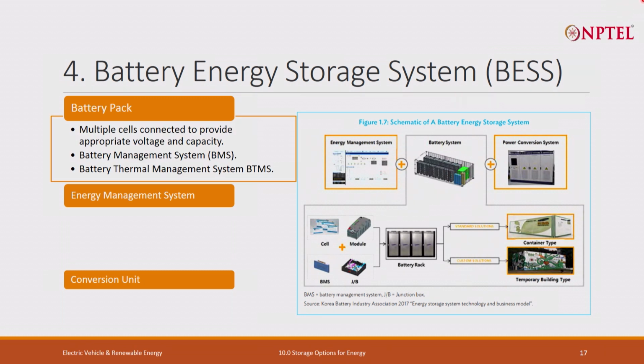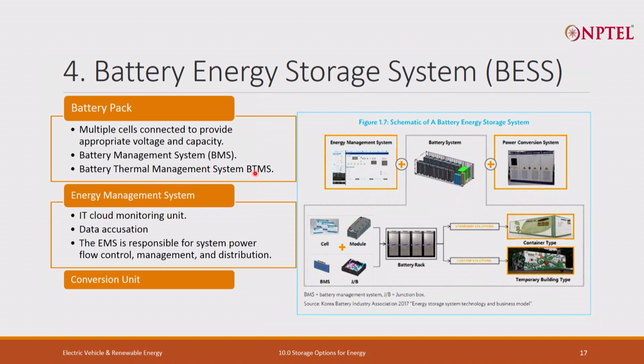In a battery pack, multiple cells are connected in series and parallel combination to provide required voltage and capacity. Then we have a battery management system, and a battery thermal management system. Then we have an energy management system with an IT cloud monitoring unit to capture the data, responsible for energy flow, its management and distribution. Then you have a conversion unit, bidirectional converters mostly, with power electronics, which converts the power flow between the grid, the battery, and the utilities.